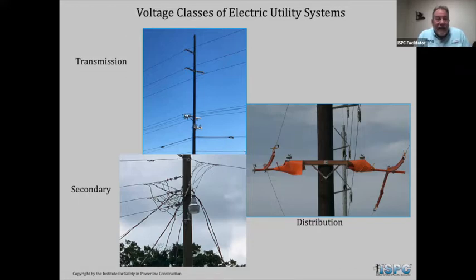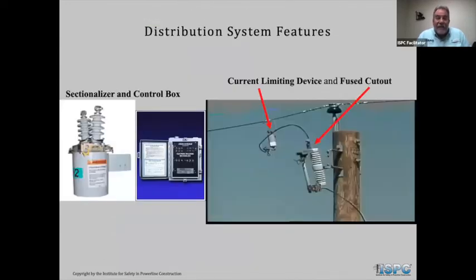And then the secondary, that's usually the biggest exposure for your workers, 120, 240, sometimes maybe 277, 480, which is a very hazardous voltage in itself. So if you had a guy that had to climb the pole and run a service off of this right below that light, the little street light presents another risk to the worker. Sometimes the grounds are not bonded real good. And if the pipe is not grounded, it could actually hold voltage while the light is on. When the light is off, it usually doesn't have any voltage to it. But like I say, usual. Is it a risk? Yes, it is.